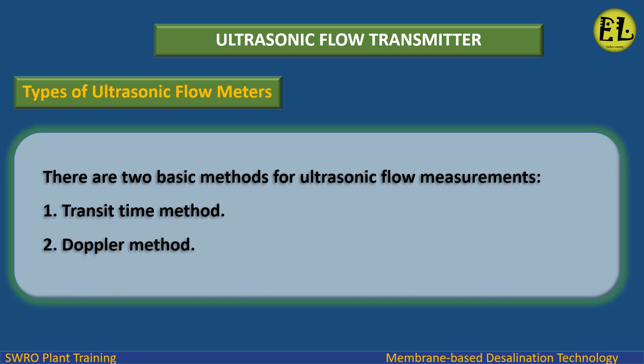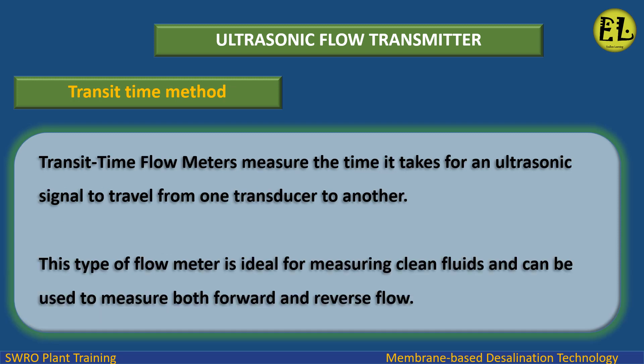Types of ultrasonic flow meters: There are two basic methods for ultrasonic flow measurements — one, the transit time method, and two, the Doppler method. Transit time flow meters measure the time it takes for an ultrasonic signal to travel from one transducer to another. This type of flow meter is ideal for measuring clean fluids and can be used to measure both forward and reverse flow.